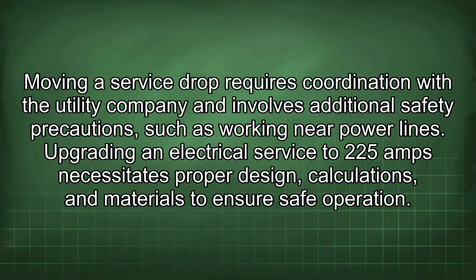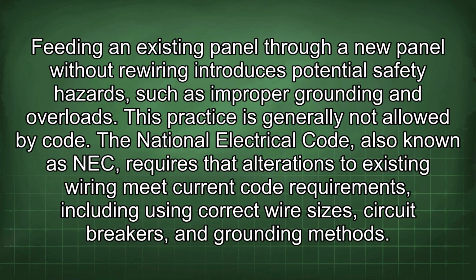Moving a service drop requires coordination with the utility company and involves additional safety precautions, such as working near power lines. Upgrading an electrical service to 225 amps necessitates proper design, calculations, and materials to ensure safe operation. Feeding an existing panel through a new panel without rewiring introduces potential safety hazards, such as improper grounding and overloads. This practice is generally not allowed by code.